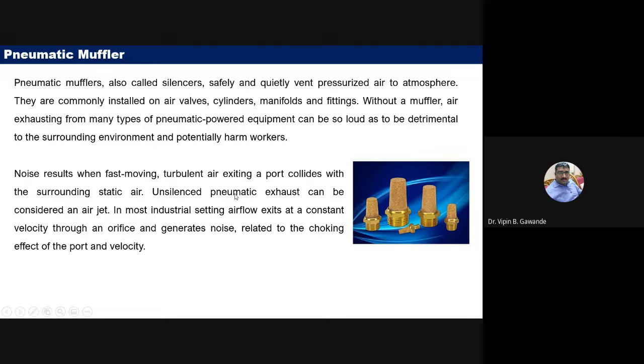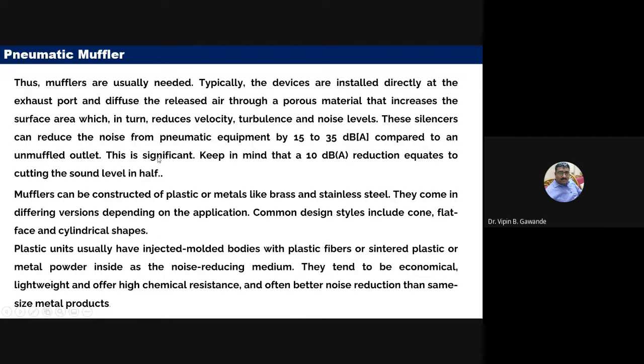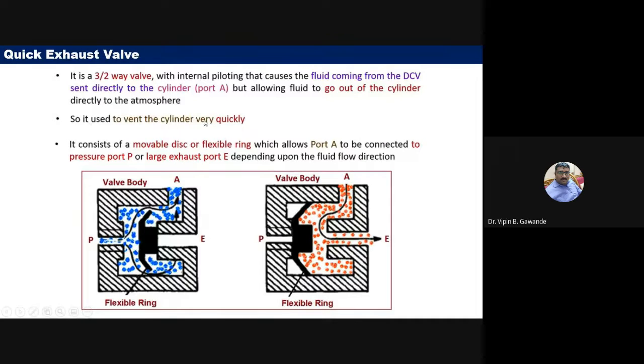Pneumatic silencers can reduce noise from the pneumatic system by 15 to 35 decibels. They are generally made of plastic or metals such as brass or stainless steel. Their common application is to safely and quietly vent pressurized air to the atmosphere, reducing sound generated by high-speed air movement.